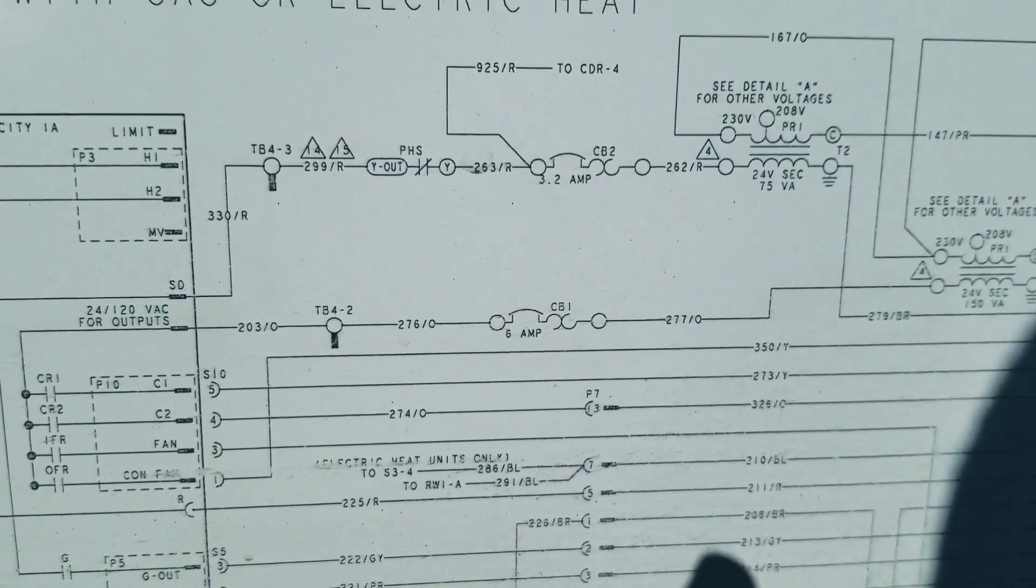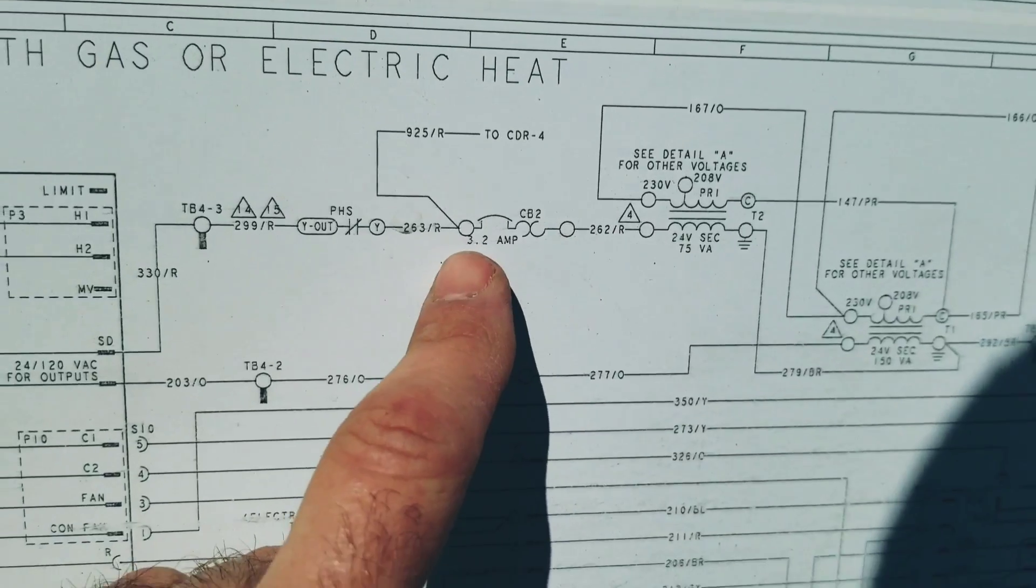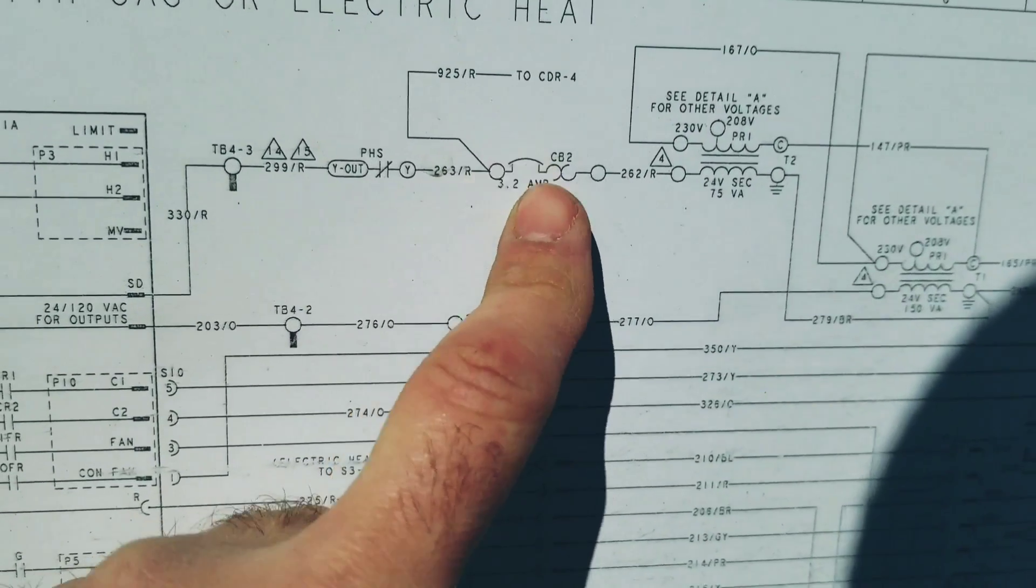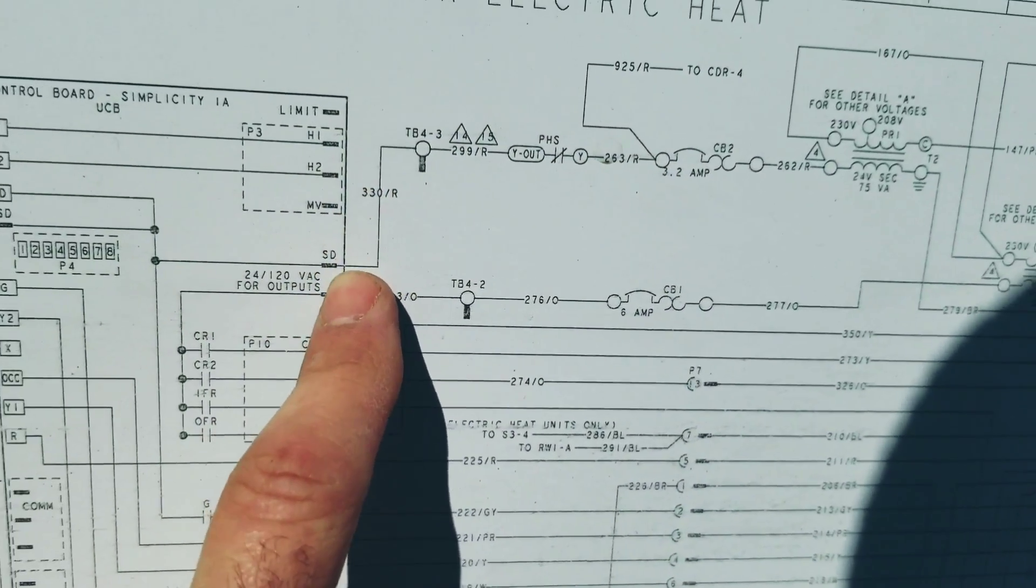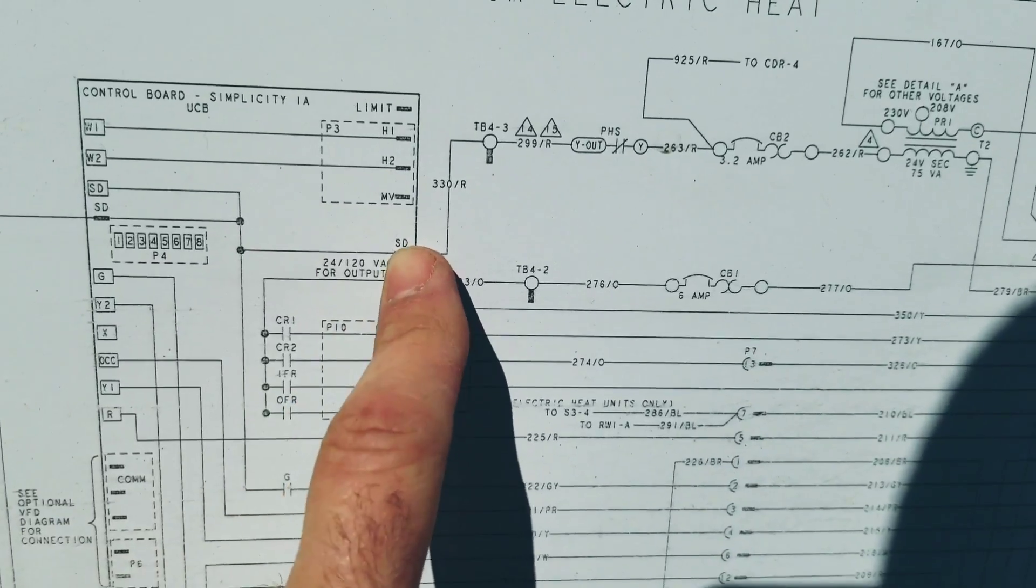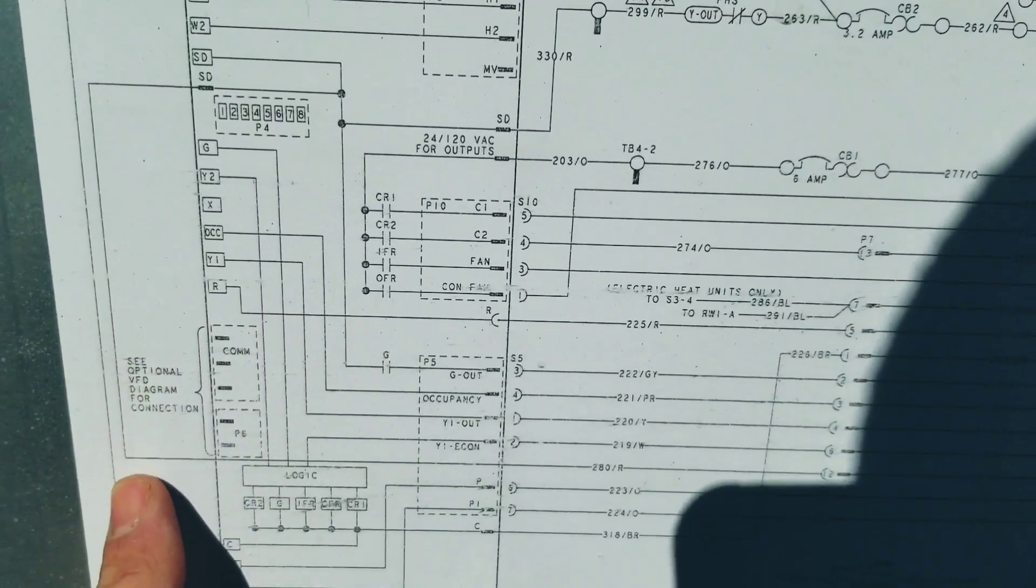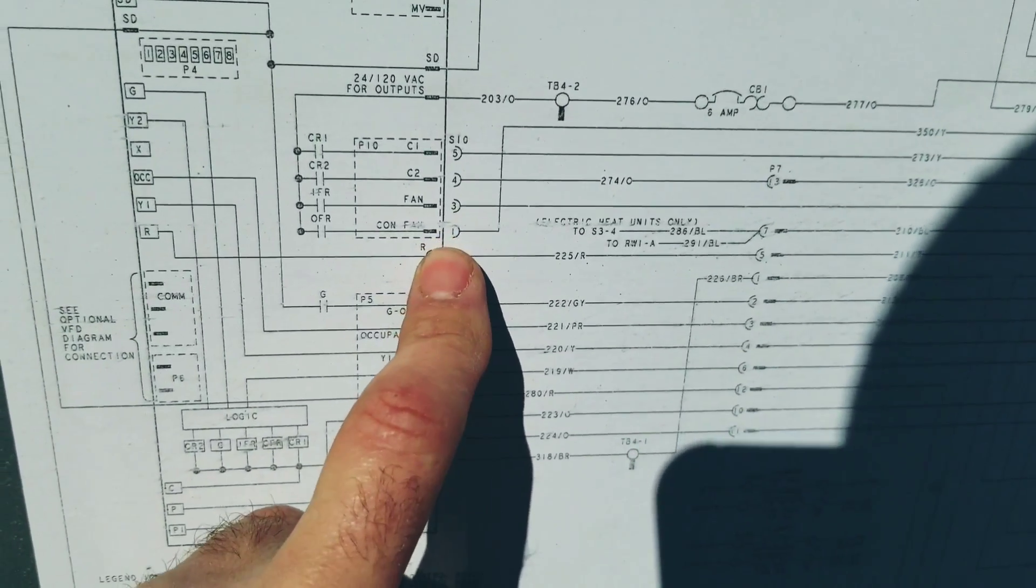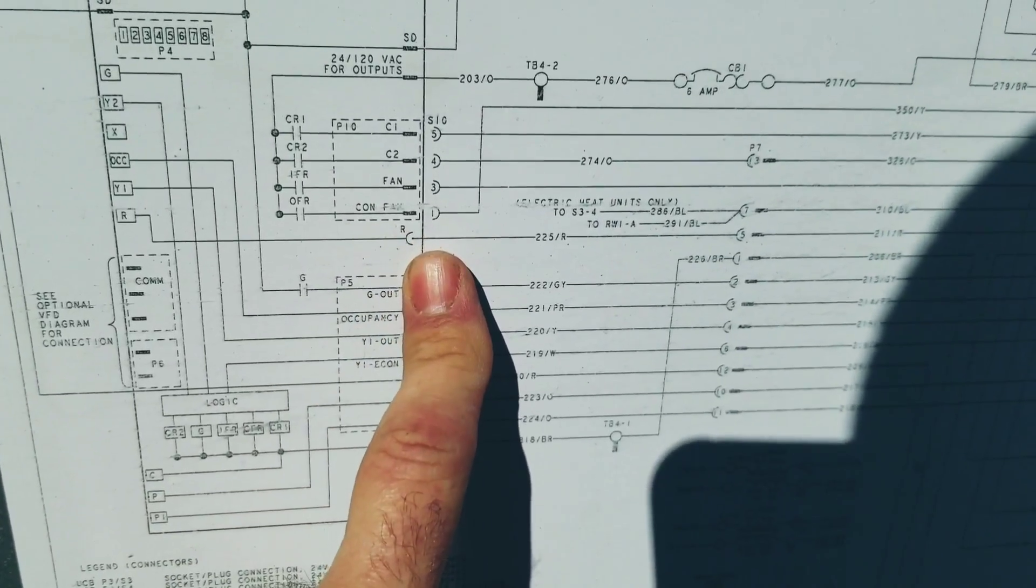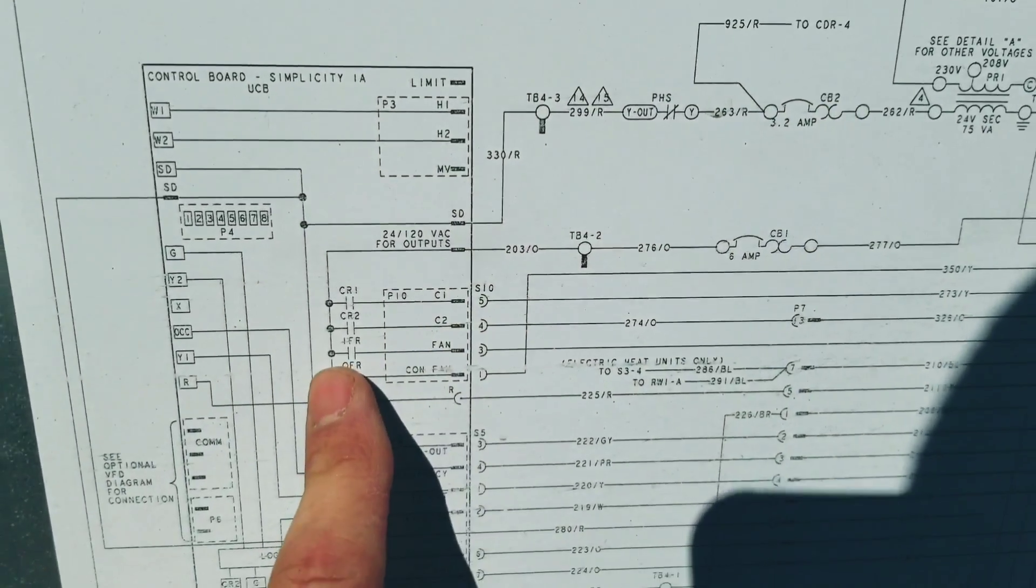If we go ahead and look at the wiring diagram, it's our low voltage circuit here. There's that breaker—we have to find out what this breaker is protecting. If we follow it, we come into the main control board. This SD is the smoke detector circuit, so it comes through here, goes out to the smoke detectors, and then comes back to R. When the smoke detectors are closed, our board gets power. That is one load that circuit breaker is protecting.